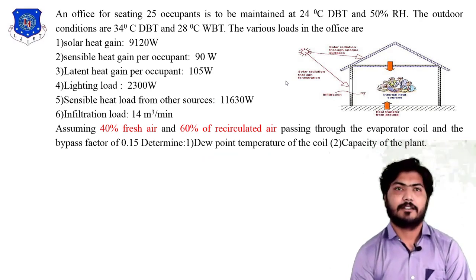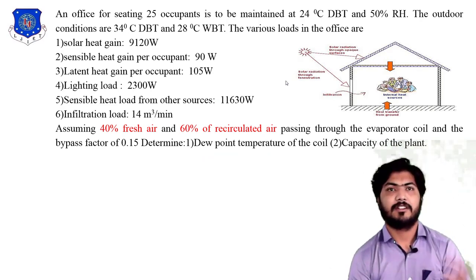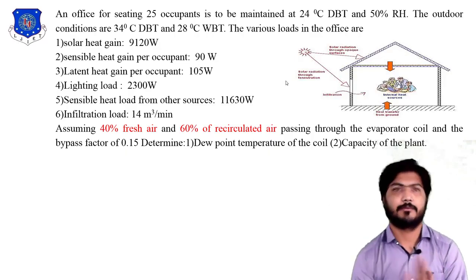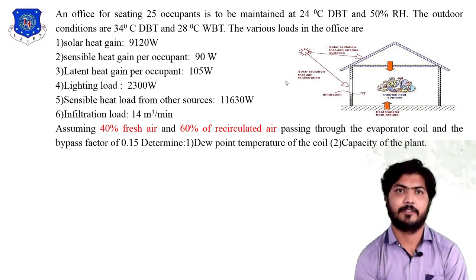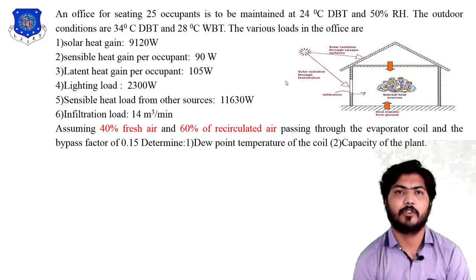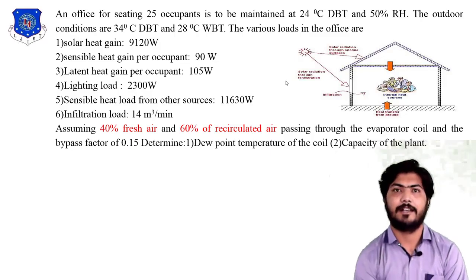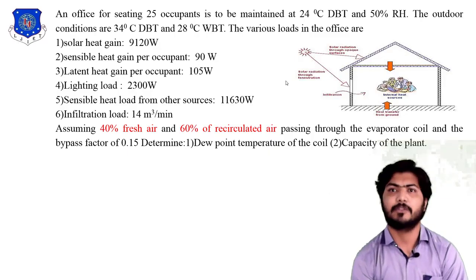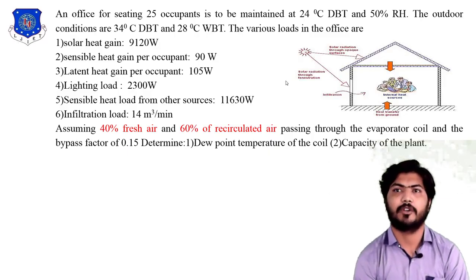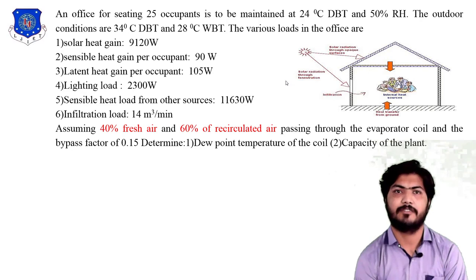Infiltration air carries both latent heat and sensible heat load, which is why the infiltration load is divided into two parts. The next condition assumes 40% fresh air and 60% recirculated air — that is the ventilation of air passing through the evaporator coil. The bypass factor of the coil is 0.15.